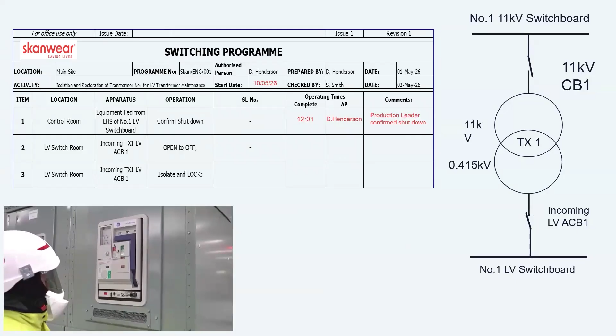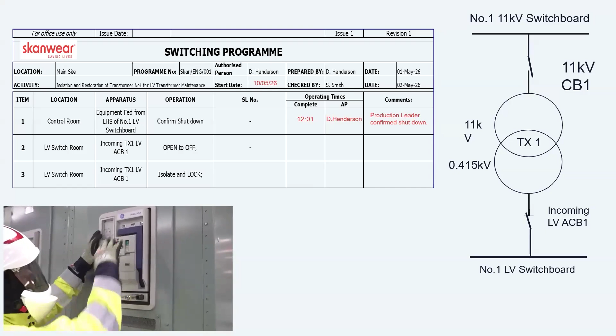So the next step I'm going to do is go to the switchgear, because I've got no remote control. And I'm going to open the circuit breaker. Verify that it's opened. I'll then update my switching program.